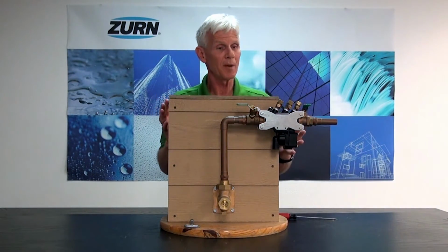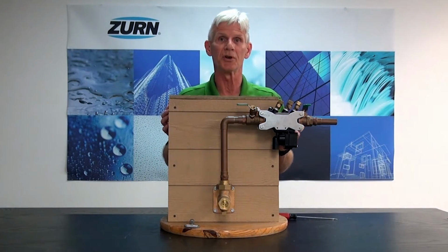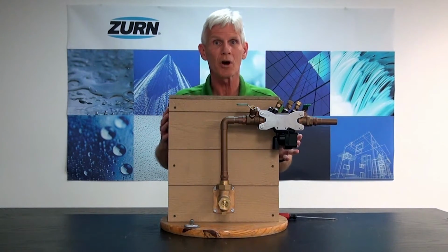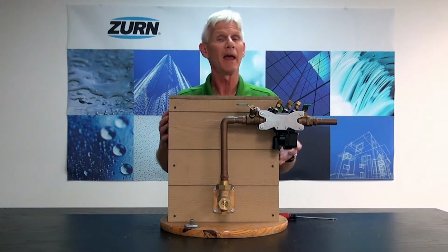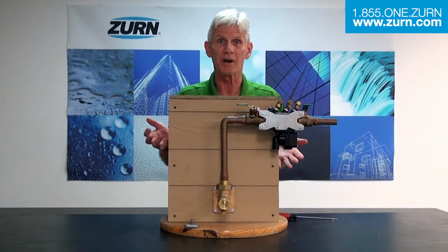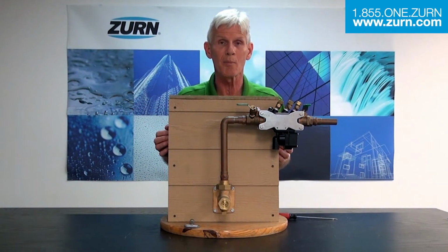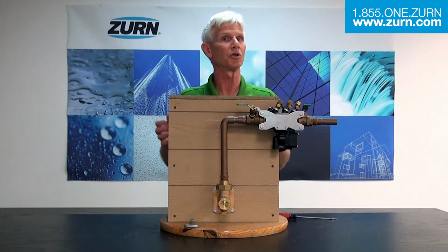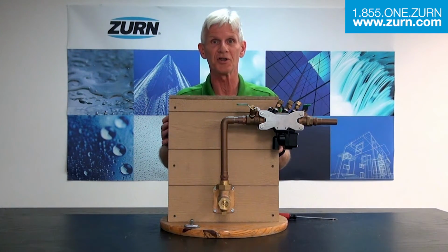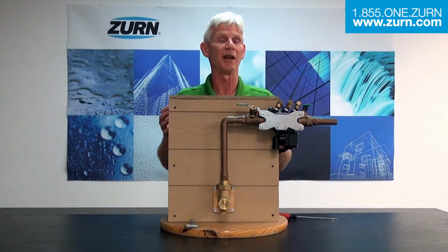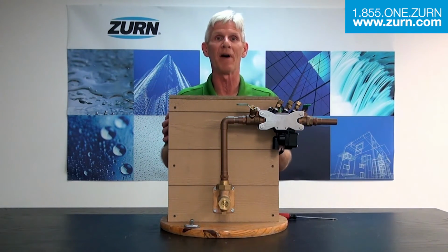Now, the great thing about this quick troubleshooting procedure is it doesn't matter if it's a 1/4 inch RP or a 10-inch RP, and it also doesn't matter who manufactures it. All RPs work exactly the same way. So this quick test can be used regardless of the manufacturer and regardless of the size. It'll help you troubleshoot and diagnose why you are getting that relief valve discharge.